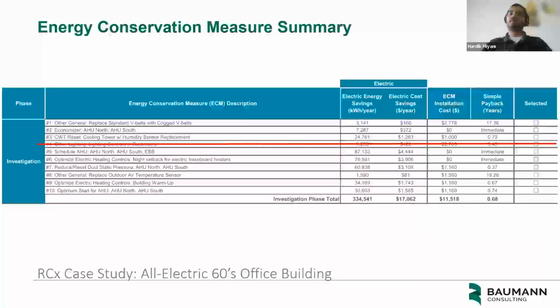After we prepared this report, we conducted an investigation review meeting with the client, where we went through each and every measure in more detail: what changes will be made in the controls or in the set points, what will be the energy saving for each ECM, what is the implementation cost, and what is the payback. After the review meeting, the client was not interested in pursuing one of the measures, the lighting controls in the restroom, because they felt it might hinder the overall occupant experience if the lights are not turning on at the right time.